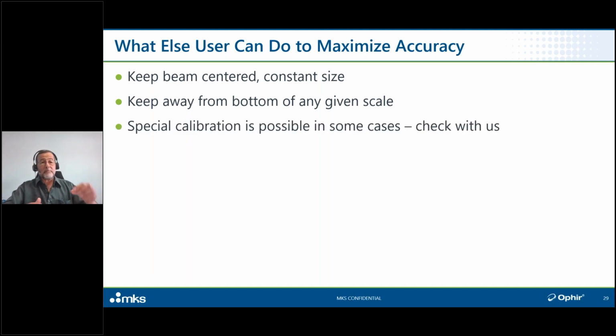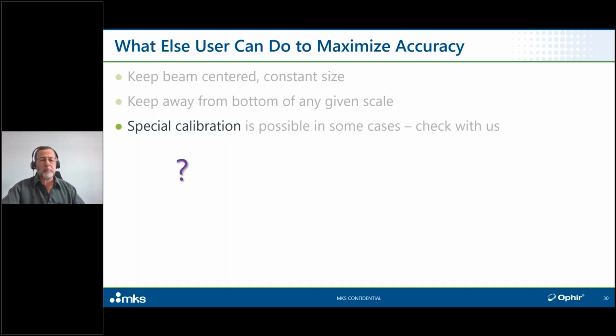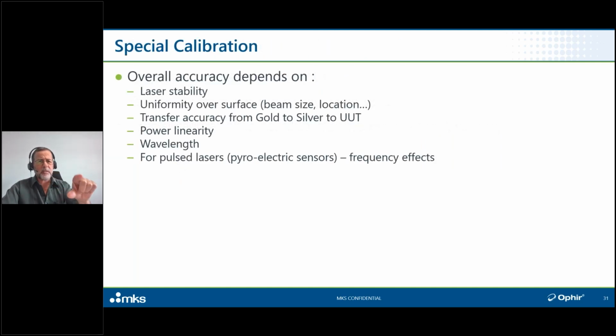If you need better absolute accuracy than what's specified, special calibration might be possible in some cases. Check with us. Now, what do I mean by special calibration? So you remember this from a couple slides ago. It's one of the things that I said to remember, that the overall accuracy of our calibration process depends on the laser stability, uniformity over the surface, etc., power linearity, wavelength, frequency effect, all of those different things. So we normally calibrate with the beam centered and filling about 1/3 to 1/2 of the aperture, as I said.